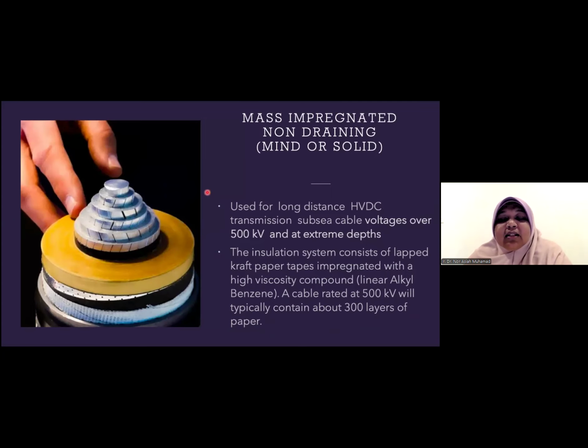Then we have the third category, which is mass impregnated non-draining, or solid insulated cable. In this cable, this is the conductor, and then this is the semiconductor. This is the paper permeated in oil. Then we have the shield, and we have another layer of insulation. It is used for long distance HVDC transmission lines and subsea cable, because there are a few connections under the sea. For subsea cable, the insulation is important because it operates under the water.